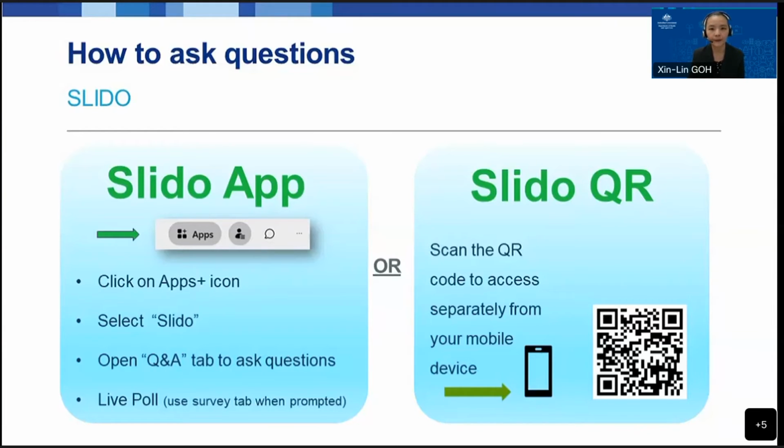Thank you. Our next question is, if the CE mark is revoked from an Australian manufacturer, can the device continue to be supplied in Australia under the TGA? So the CE marking is something that is of relevance in Europe, but within Australia, it will be whatever is relevant within the Australian medical device framework. So if they do hold a relevant conformity assessment certification that is being recognized and is still valid under our framework, then there's no problems in supplying those devices.